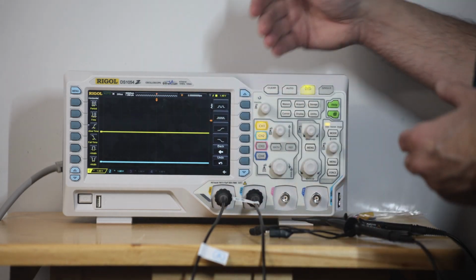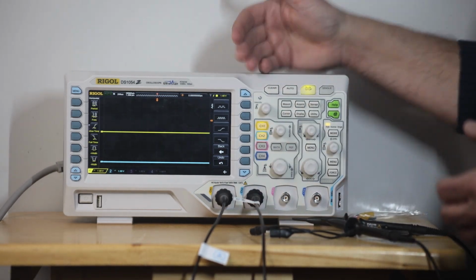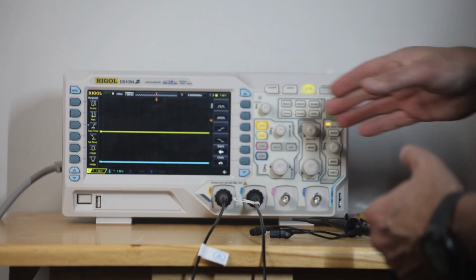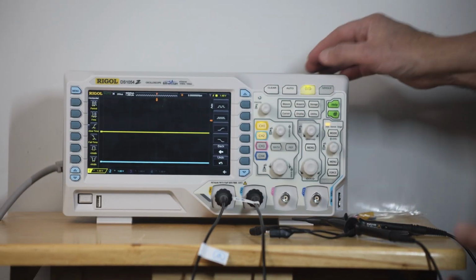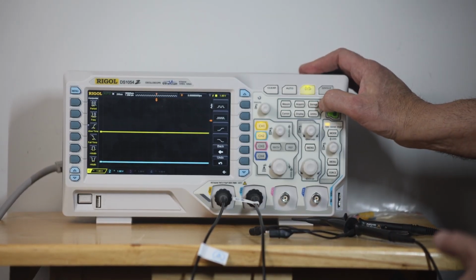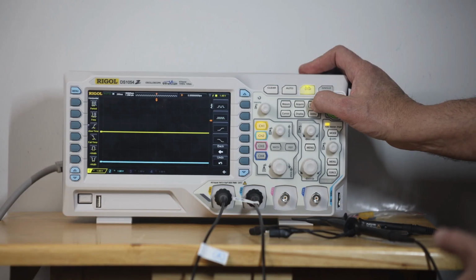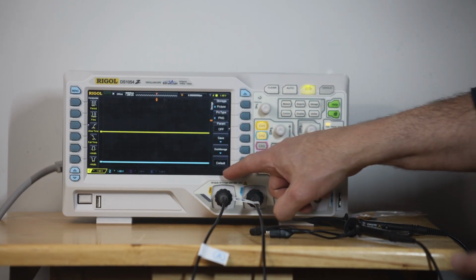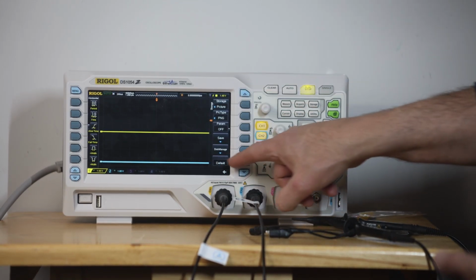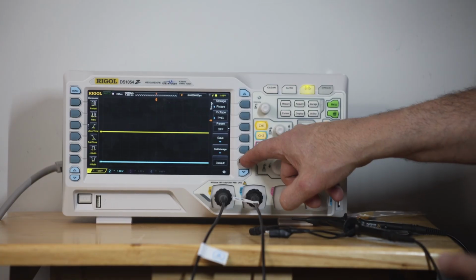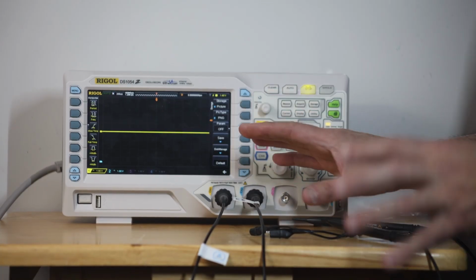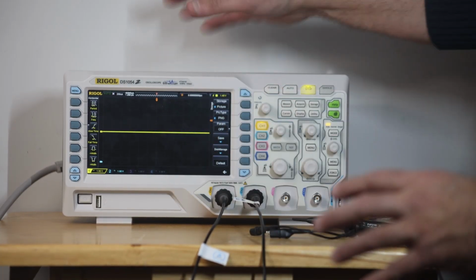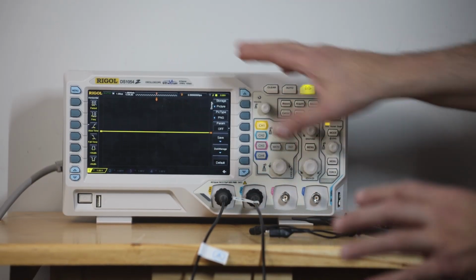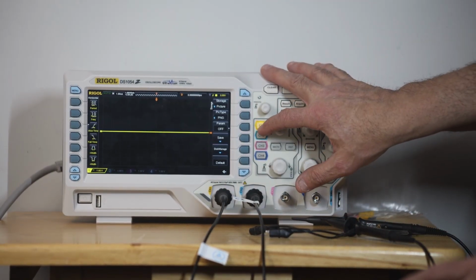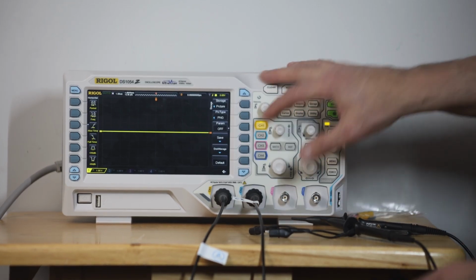But sometimes you want to reset even the settings that are on the inside and reset the screen itself. So when you're doing that, there's a storage button in the upper right-hand corner. You push that, and then this here goes to default, and you push the blue button, and give it about 5 seconds or so, and it's going to reset the internals, and it's also going to be resetting the screen. So we can tell that it's done now because it just went to channel 1 and channel 2 is off.